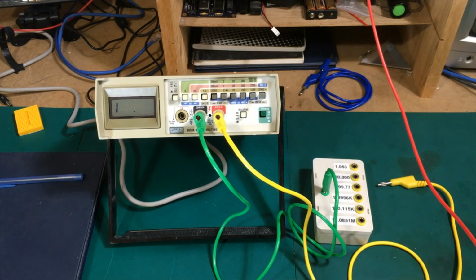So if you look at one of the ranges, it's dependent upon the other. For instance, if the resistance ranges are all okay, that's an indication also that the DC ranges are okay as well. And if the DC voltages are okay, then the DC current is going to be okay. So you only have to look at a few things.